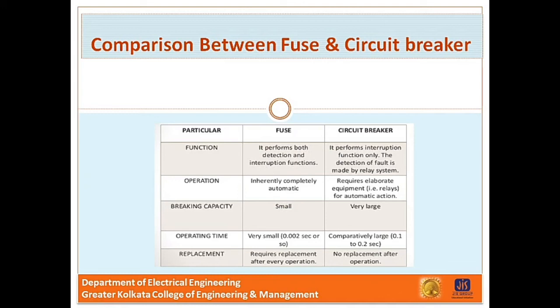Next one, operation. Now the fuse is an inherently completely automatic device, but the circuit breaker requires elaborate equipment for automatic action. Okay, breaking capacity: the fuse has small breaking capacity, whereas the circuit breaker has large breaking capacity. The operating time in the fuse is very small comparatively to the circuit breaker. This is an advantage of the fuse. The operating time is nearly 0.002 seconds or like that, and for the circuit breaker the operating time is 0.1 to 0.2 second. Replacement, now the fuse requires replacement after every operation, that is very problematic.